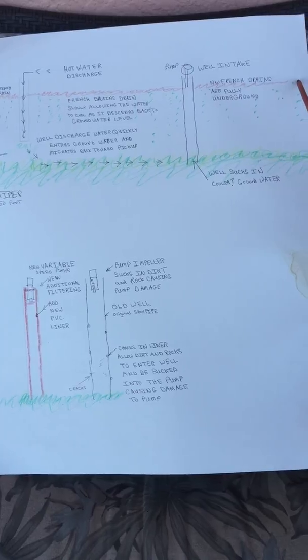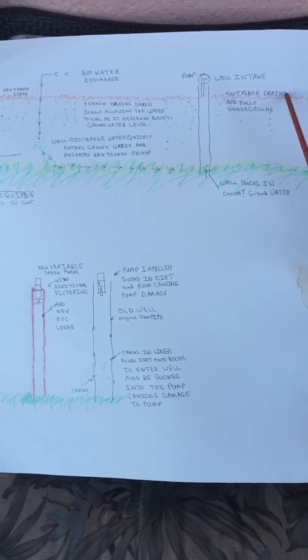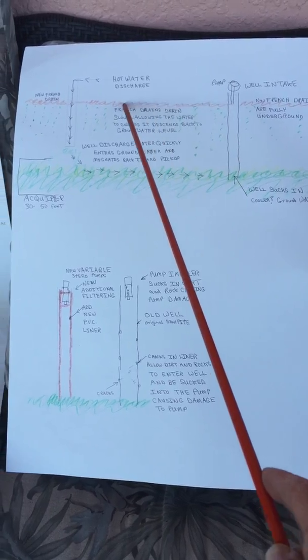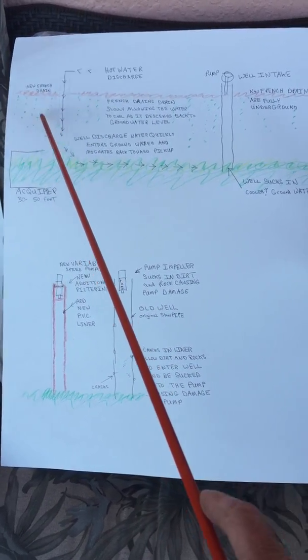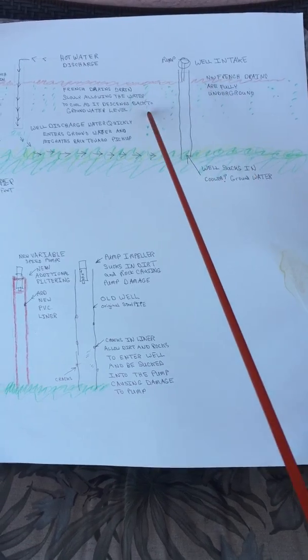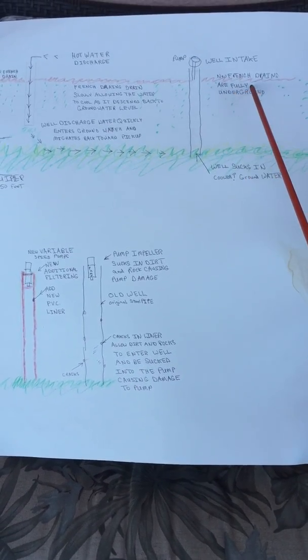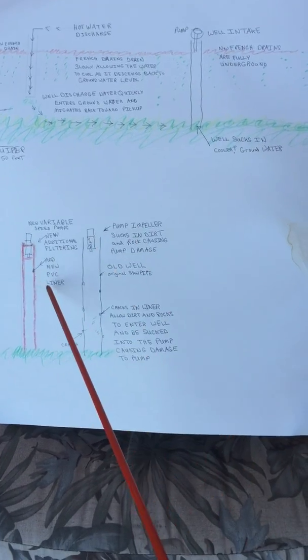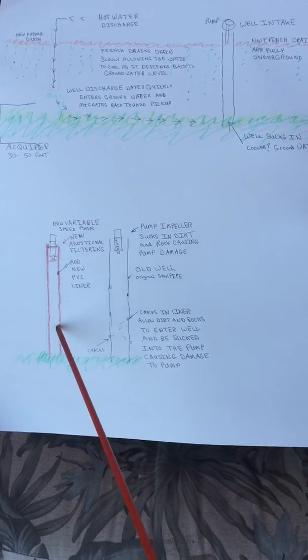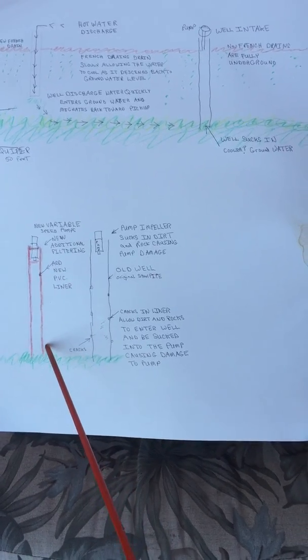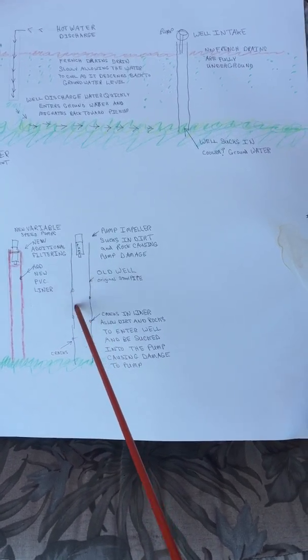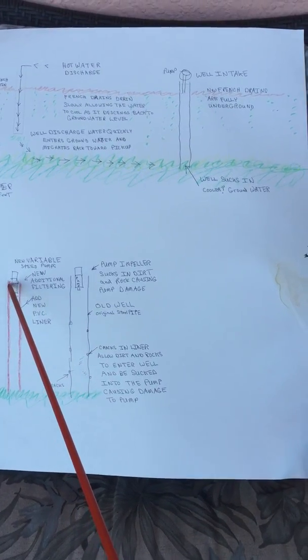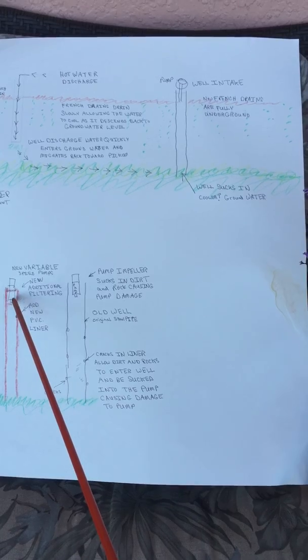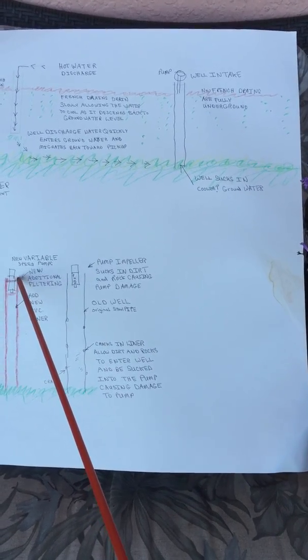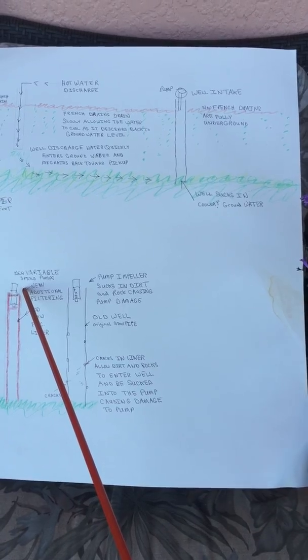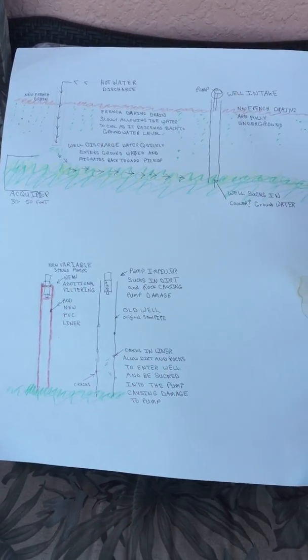By installing French drains, which are essentially leaky pipes 1 or 2 feet underground, the water will slowly drain down into the aquifer and cool off as it's going through. This is not a big deal to put in. By adding PVC liners on all the wells, plain old PVC pipe, it'll prevent the cracks and dirt and rocks from being sucked in and destroying our pumps. Also, additional filtering to prevent any dirt from getting in should solve a lot of the problems and could actually keep us going for quite a while.